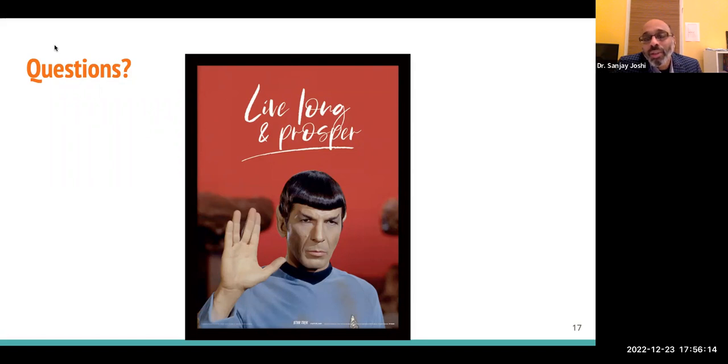The other thing to consider is if there is metal in your implant, how much metal there is and how much heat it can cause if you are doing an MRI scan. Some of these you may actually have to test by experiment: literally put your implant inside an MRI scanner, take a scan, and measure the temperature.